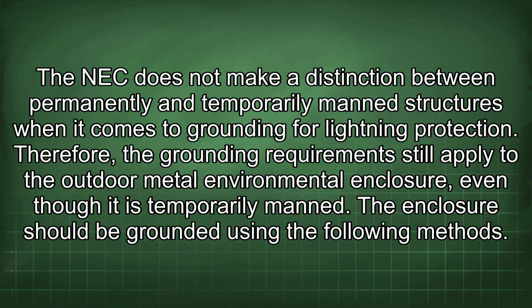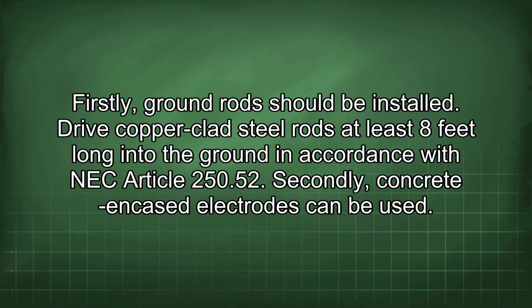The NEC does not make a distinction between permanently and temporarily manned structures when it comes to grounding for lightning protection. Therefore, the grounding requirements still apply to the outdoor metal environmental enclosure, even though it is temporarily manned. The enclosure should be grounded using the following methods. Firstly, ground rods should be installed. Drive copper-clad steel rods at least 8 feet long into the ground in accordance with NEC Article 250.52.